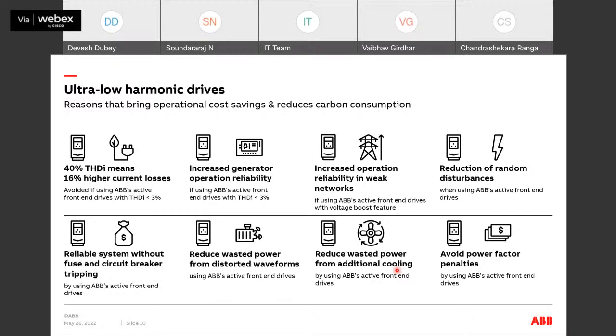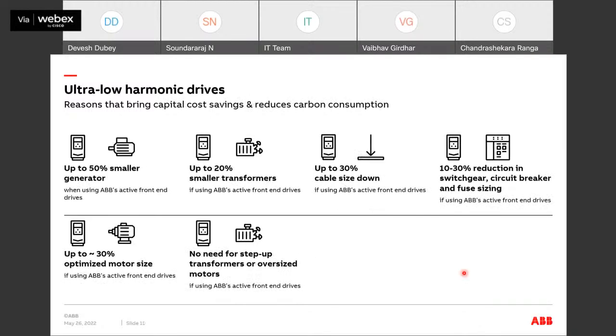And we can avoid the penalties which come due to the power factor, which is a huge loss to the cement industries. When power factor is lesser, electrical companies push penalties on that. That can be avoided. We can have a 50% smaller generator. Transformer, as I told you, we can reduce the transformer size up to 20%. We can have a reduction in the cable size also up to 30%. We can have 10 to 30% reduction in the switchgear, circuit breaker, and fuse sizing.